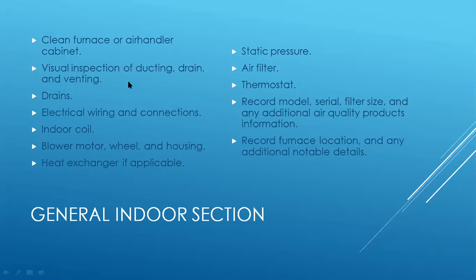There again, since you're at the indoor section, you want to do a visual inspection of ducting, drain, and venting. Does anything stand out? You know, if it does, make notes of that. And then drains. Now, this is the way I always do it. Some guys will use nitrogen. What I would always do is go to the highest point of the system, the highest point of the drain, and then I'll take, used to carry a little bottle of water, and I'd actually fill it up between calls.